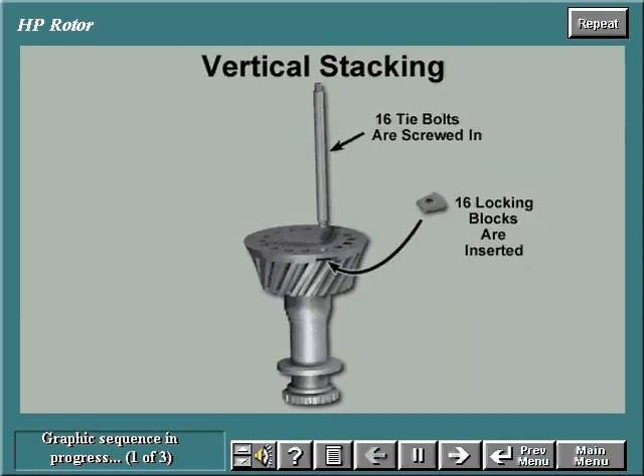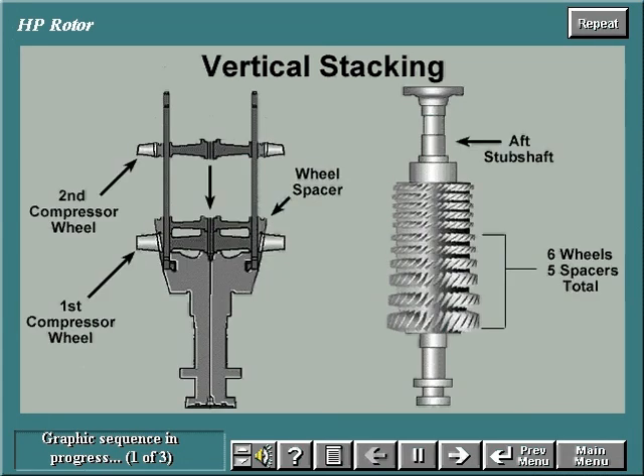Locking blocks are inserted in the tie bolt cavities in the forward stub shaft. Tie bolts are screwed into the locking blocks. The forward stub shaft is then placed in the stacking pit with the tie bolts in the vertical position. The first compressor wheel is slid over the tie bolts, then a wheel spacer and the next compressor wheel are slid into place. This is repeated until a total of six compressor wheels and five spacers are assembled.